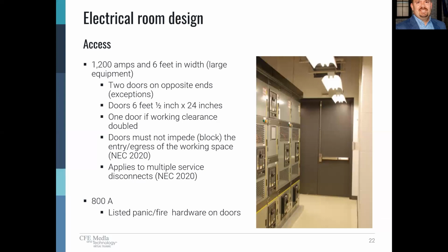Doors must not impede or block the entry or egress out of the working clearance. And the doors must be listed with panic or fire rated hardware on the doors for equipment over 800 amps. And this applies to multiple service disconnects as well.